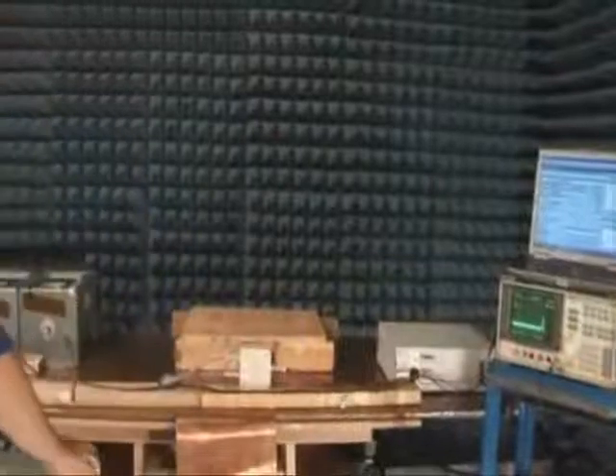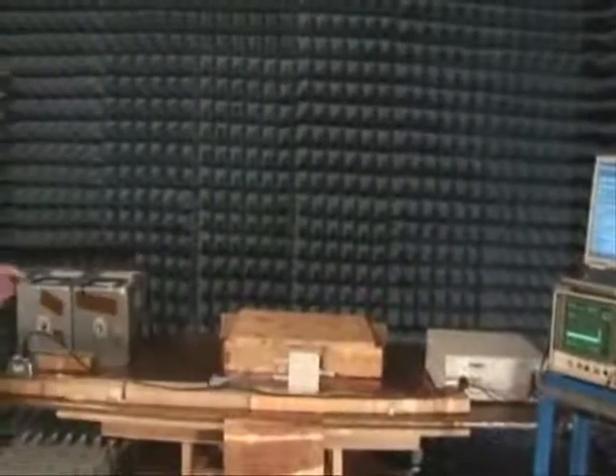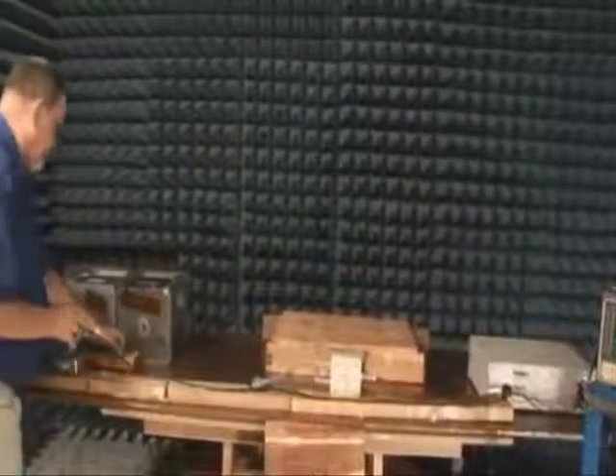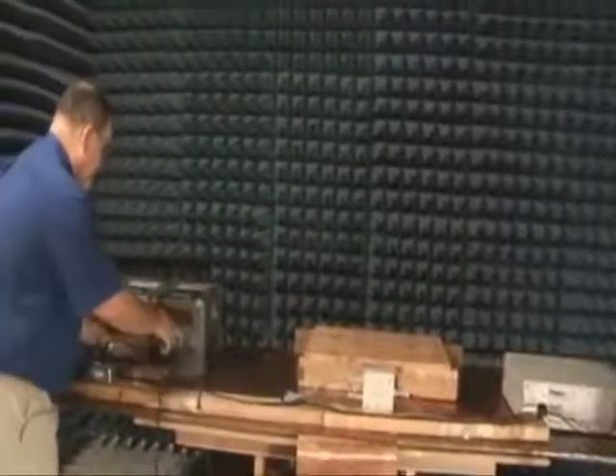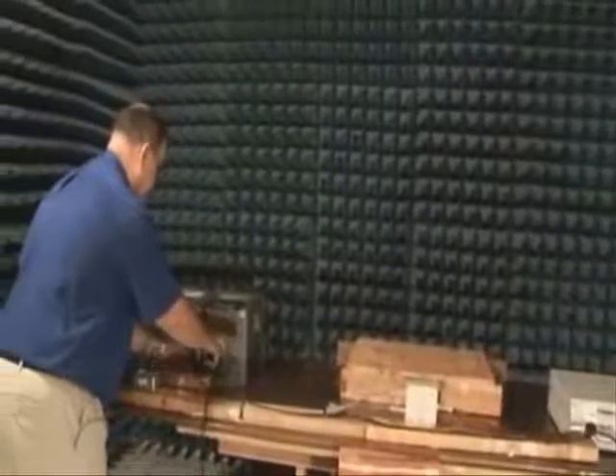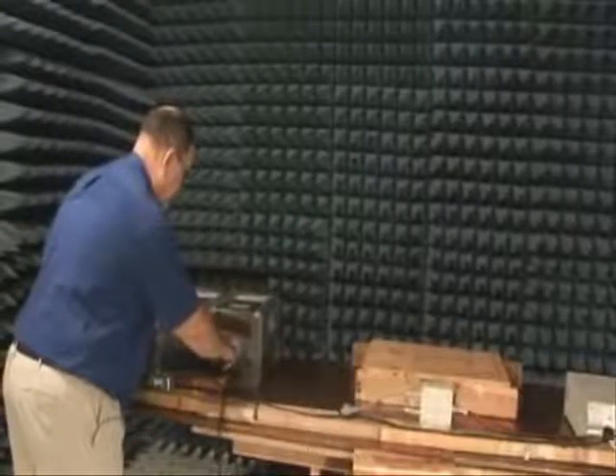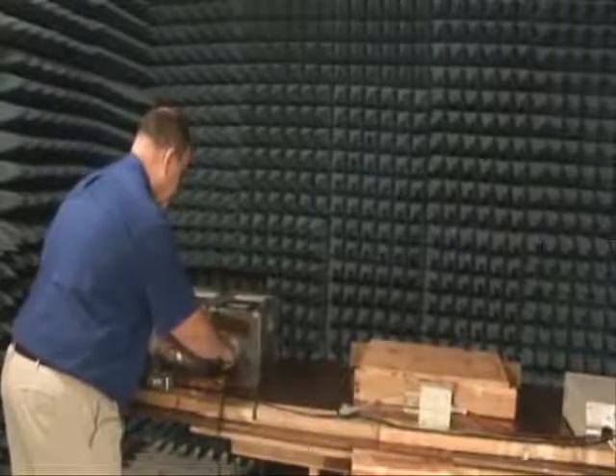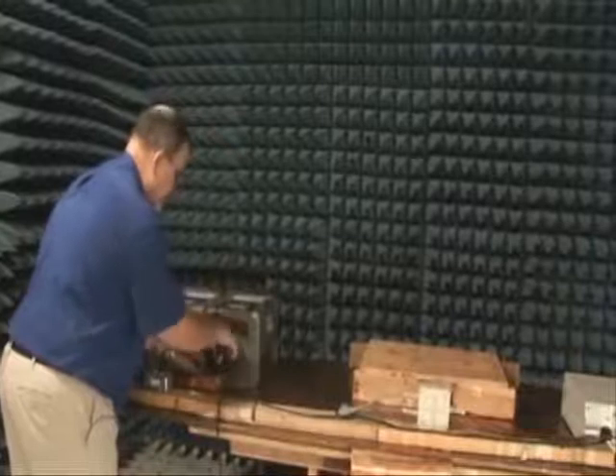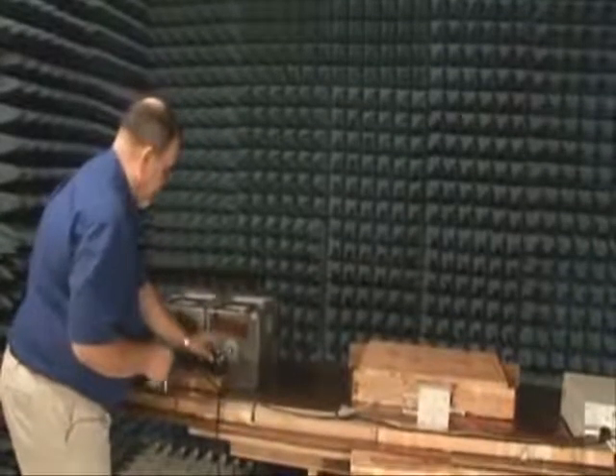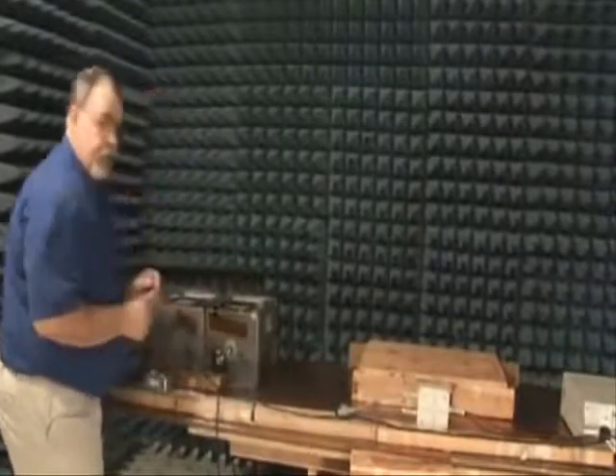And we come over to the network. And remember that now we're exposed to live terminals, so we kind of stay away from them and use caution. I've selected the phase lead for testing. I place that in the current probe, observing some basic safety. I stay away from those terminals. And I verify my position is 5 centimeters from the terminal. We know this by eyeball, virtually. And so now we are connected with the cable and probe that we calibrated. And all we have to do is run the software to collect the data at this point.